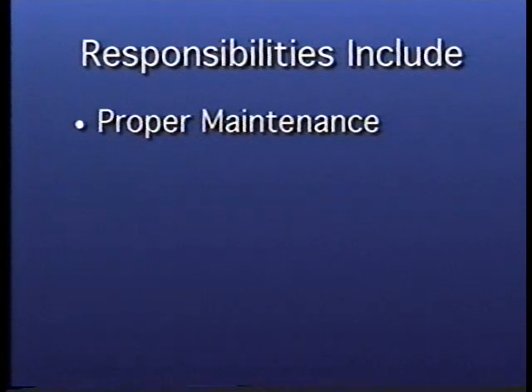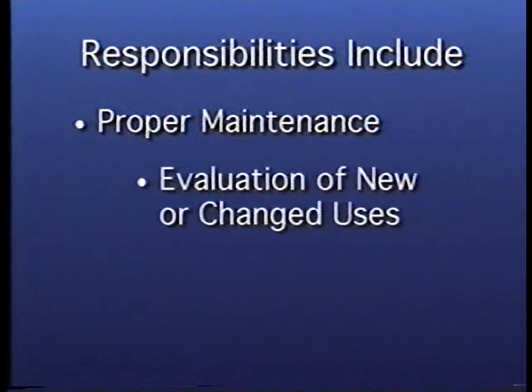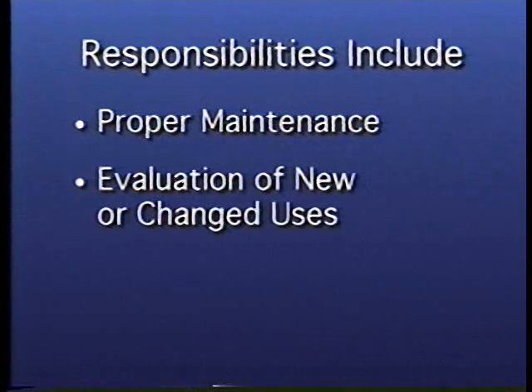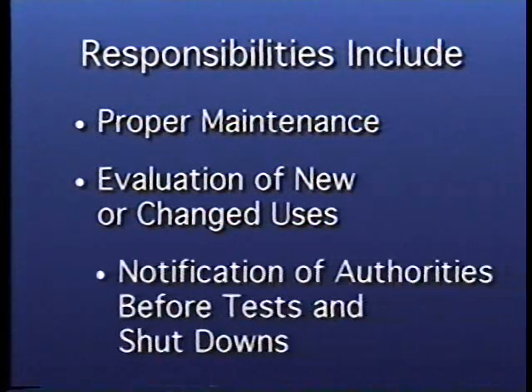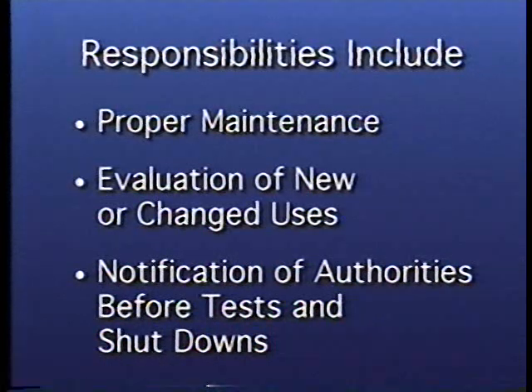Both the Fire Protection Handbook and NFPA 25 clearly state that the owner or the owner's designated representative is responsible for properly maintaining the fire sprinkler system. NFPA 25 also charges the building owner or occupants with the responsibility of evaluating fire protection systems for the capability to protect new or changed uses. NFPA 25 further requires the owner or occupant to notify the authority having jurisdiction, usually the fire department, and other authorities before testing or shutting down a system or its water supply.